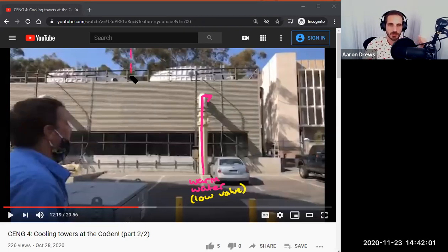Also, there's kind of an imaginary division here. There's two cooling towers next to each other. Once it goes inside of there, as Tom said a moment ago, it hits what's called a manifold. So inside of here is a pipe. That water spreads out inside that pipe. There's pipe flow again. And then it rains down through the tower. It's a little bit higher than I've drawn it right here. Once it goes through the manifold, it's sort of spread out. It has a very high surface area. It's split up into droplets.